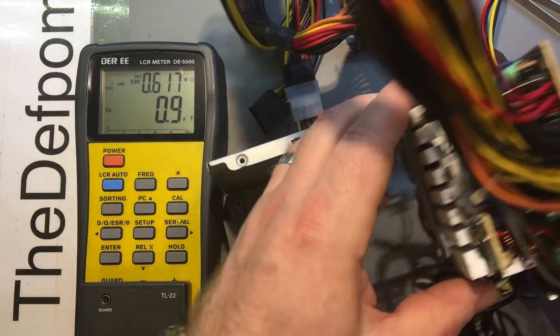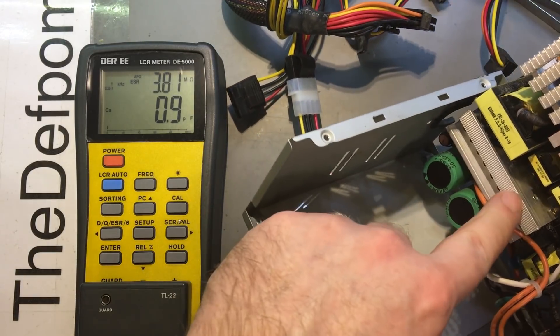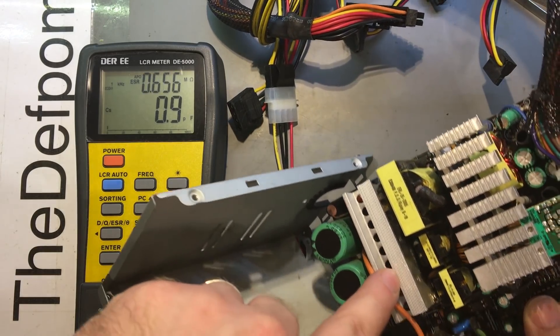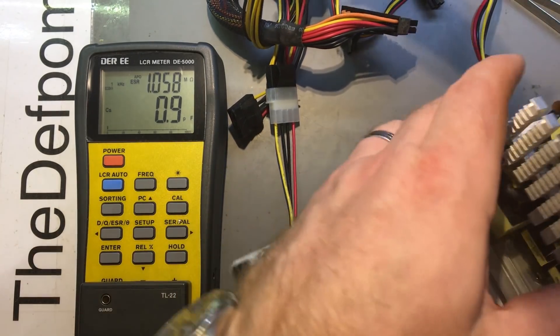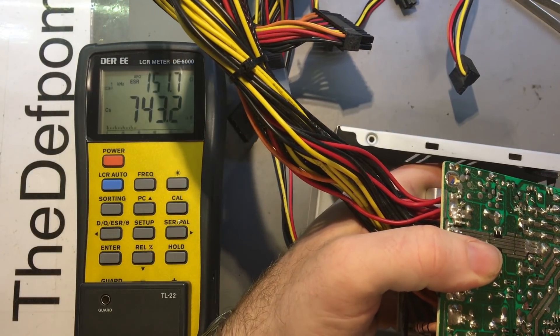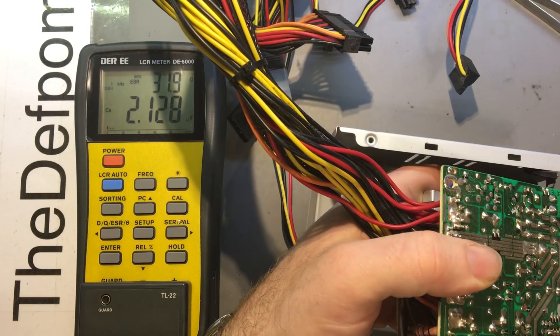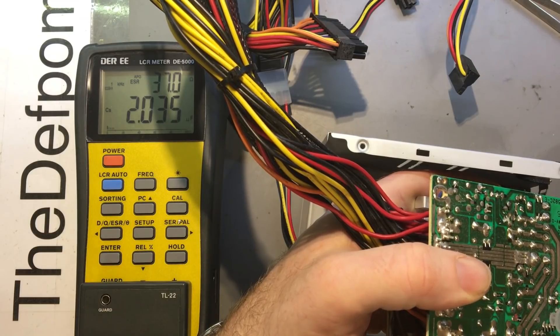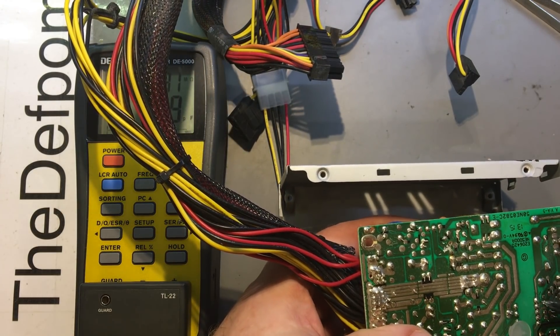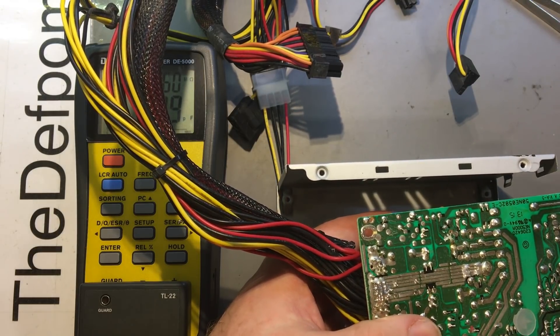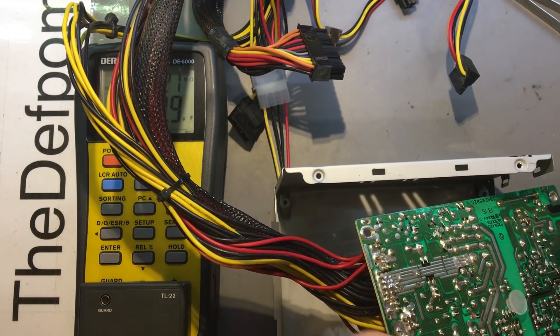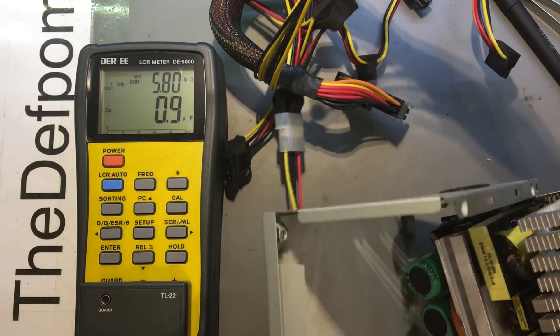Let's keep going. There's a couple tucked down in between the heat sink and the coil just down there if you can see them, potentially heat damaged. So let's see what we get. 2.1 microfarads, 31 ohms looks a bit high doesn't it, and 37 ohms, 2 microfarads so I'm also suspicious about these ones. All things being equal there should be about 15 same as the ones over here so they're probably wrong. They're probably going off value before it actually fails completely.